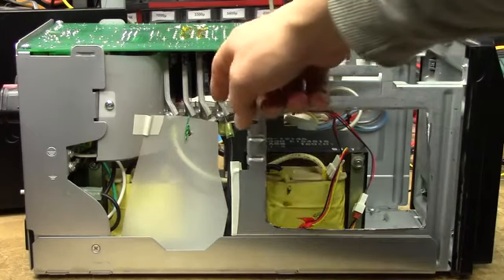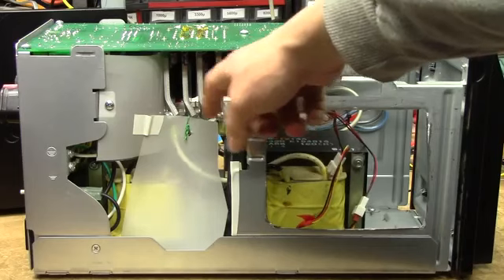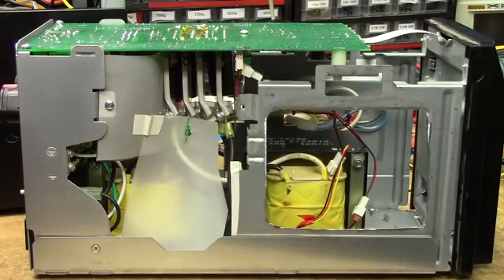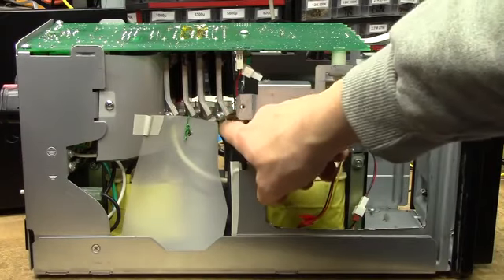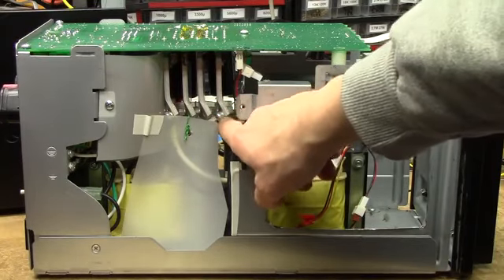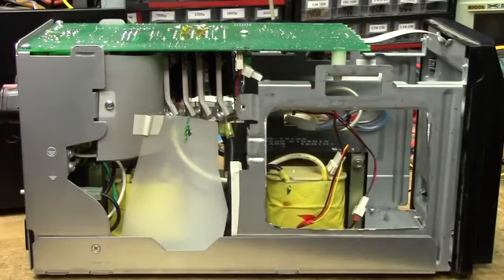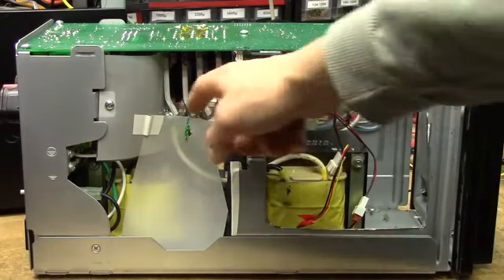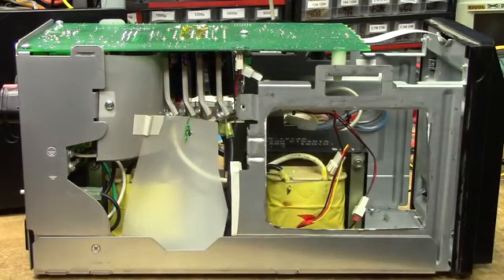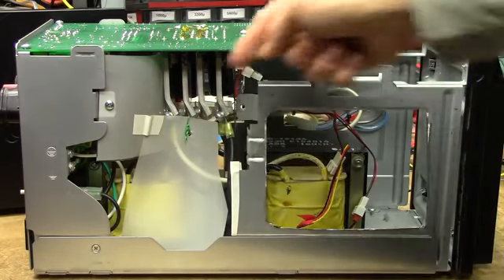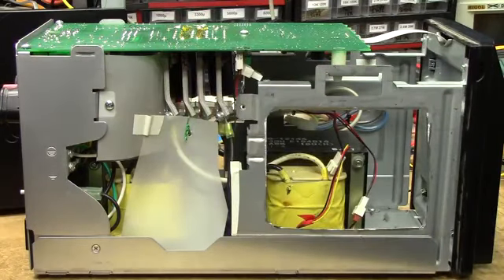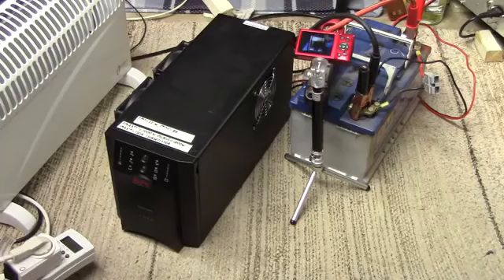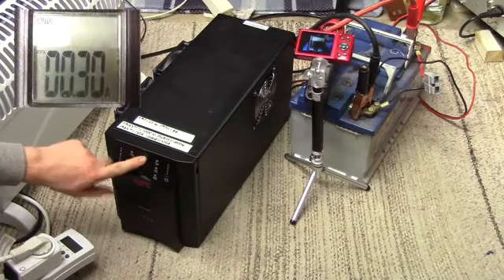You also have giant high current connections here at the heatsink at the output of the inverter, and you need to make sure that this area is extremely clean and extremely flat, else you'll basically have that catching fire. I had to replace one of these air guides once due to the white wire connection there just going so hot it melted it and it went all horrible.